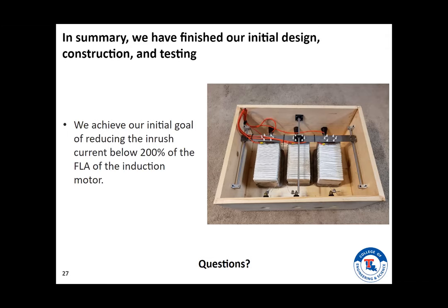Did y'all happen to look in y'all's research at the difference between VFDs and soft starters, and when it's appropriate to use a soft starter versus a VFD? Yes, we did. We typically found that VFDs were much more appreciated in applications where some degree of speed control was necessary, whereas soft starters were typically more geared towards operations that were fire and forget, where you start them up, and then after they've started up, you just want them to run at a constant maximum pace.